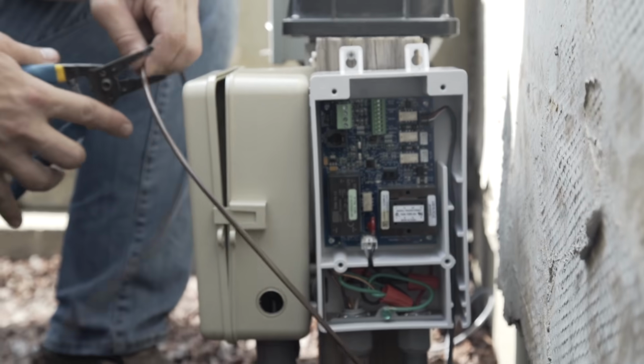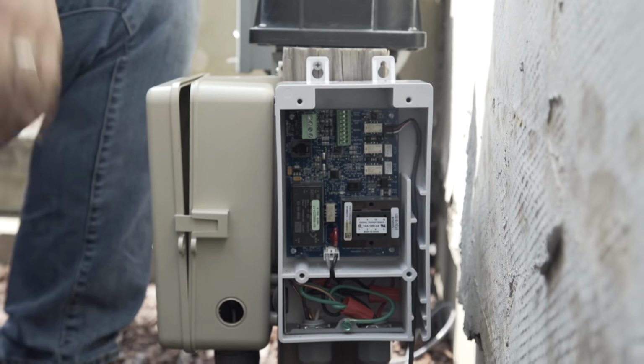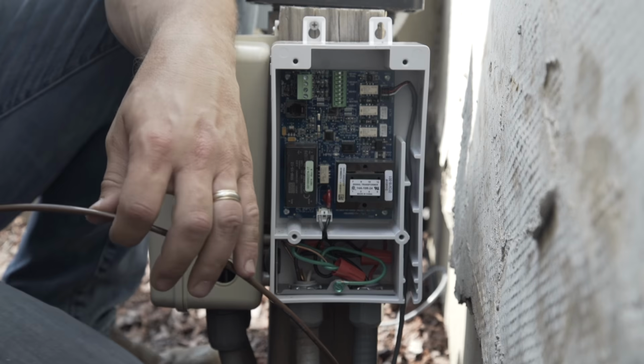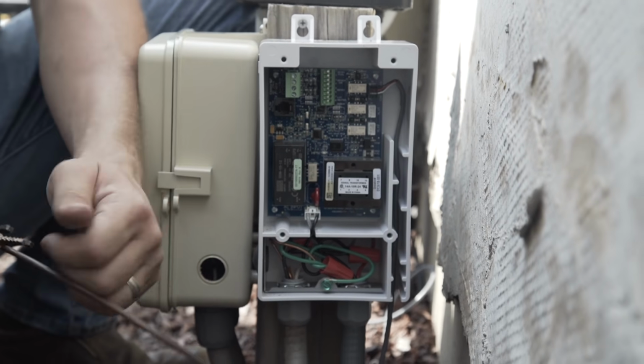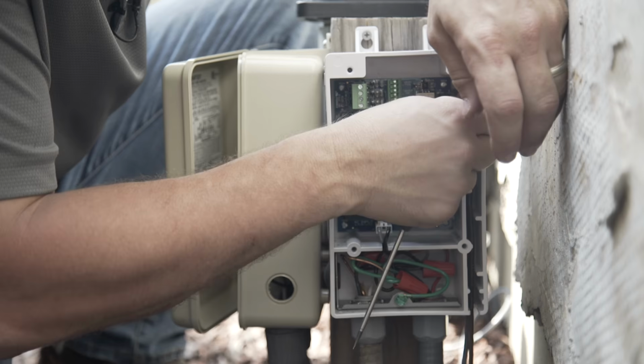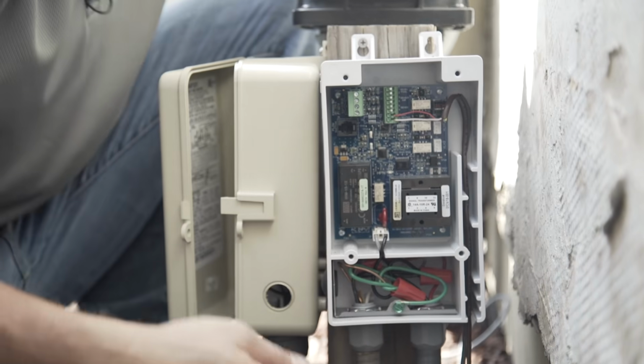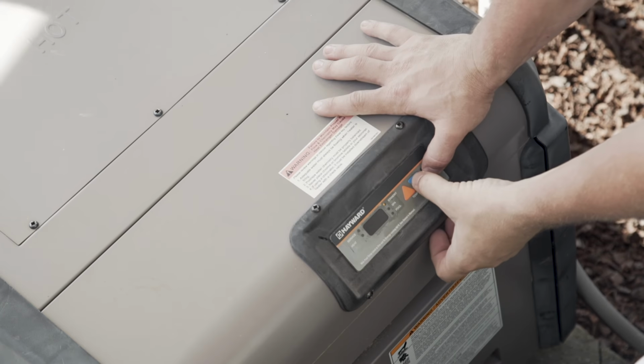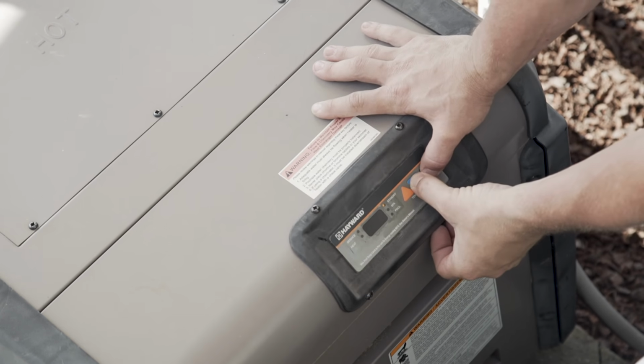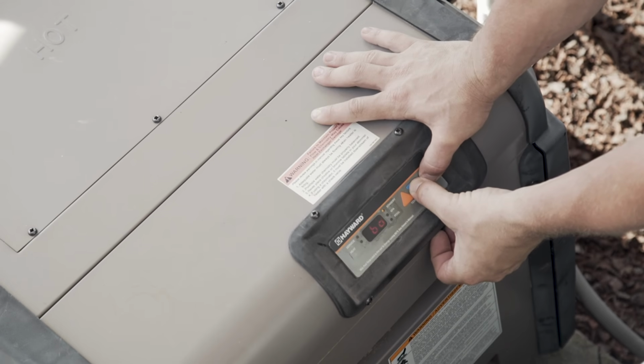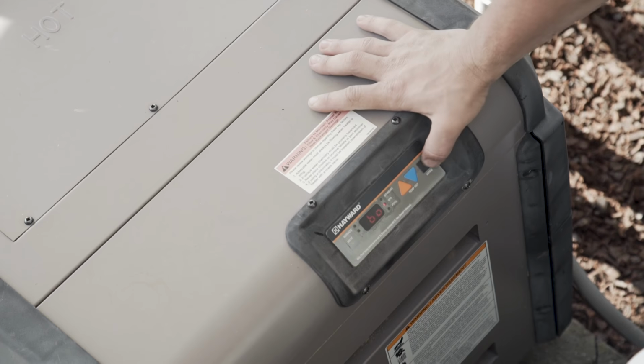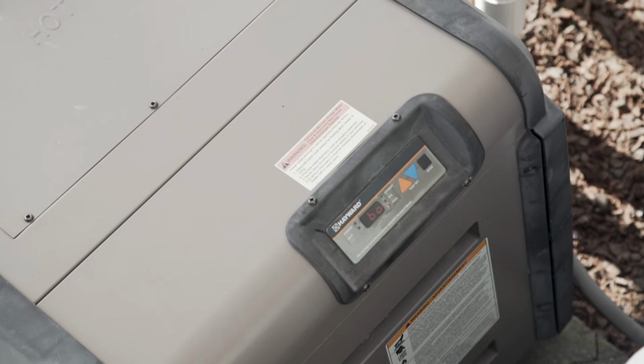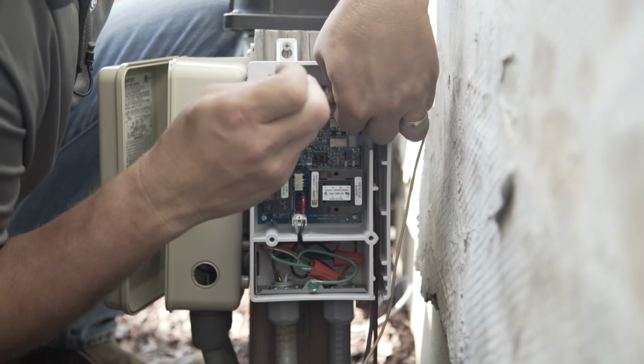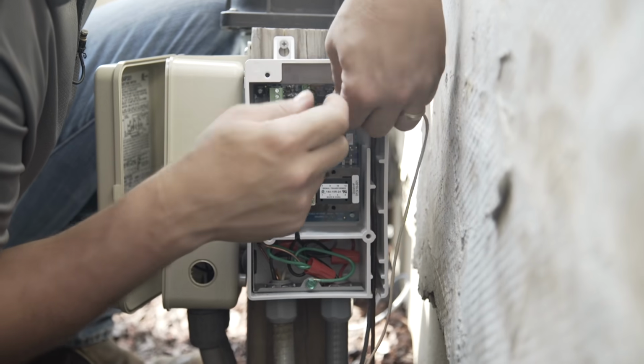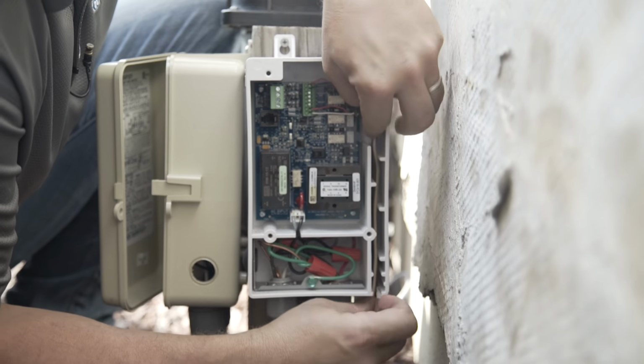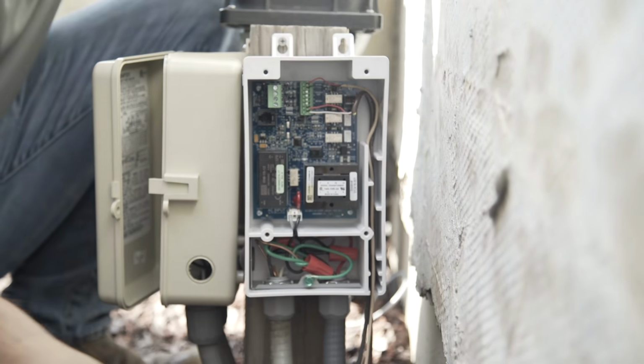To connect Hayward's universal H-series heater to the VS Omni system, first, obtain a 2-wire, low-voltage cable from your local electrical supply center. On the heater, wire the low-voltage 2-wire connection into the terminals under white and orange as shown. Using the heater manual for your heater, put the heater in bypass operation. You know you are successful when a BO appears on the heater's keypad screen. If not in bypass operation, the control will not work correctly with the heater. The final low voltage connections include the actuators and temperature sensors. As shown before, these wires should be nested into the low voltage raceway and should not be run with any high voltage wires.